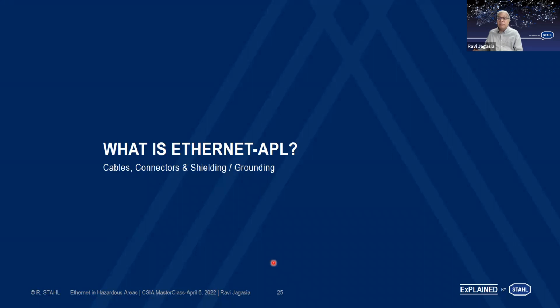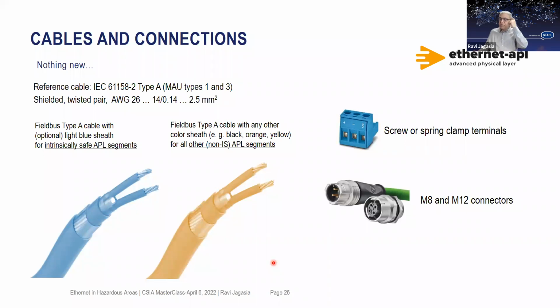We talked about cables and connectors, and then we need to be talking about shielding and grounding also. We talked about cables. We talked that we'll be using a Fieldbus type A cable. When you're using a Fieldbus type A cable, you will be ensuring that these are good enough for IS applications, are twisted and are constructed very well, and have the low L and C characteristics so that they are not a source of hazard when you're transferring power over the cables.